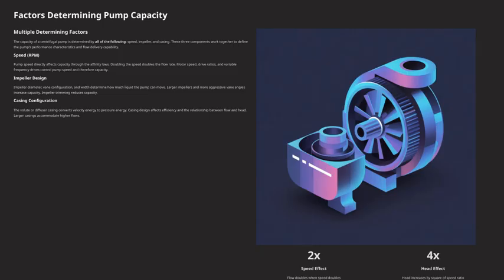The main elements are speed, impeller, and casing. These three components work together to define how well the pump performs and how much fluid it can move. First, regarding speed, or RPM, rotations per minute, this directly impacts capacity thanks to the affinity laws. When we double the speed, the flow rate also doubles. So, controlling the motor speed, drive ratios, or using variable frequency drives allows us to adjust capacity effectively.